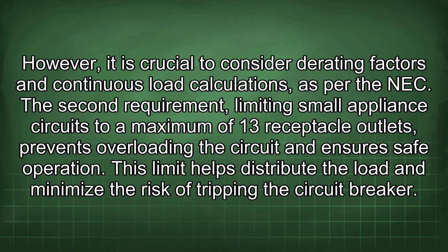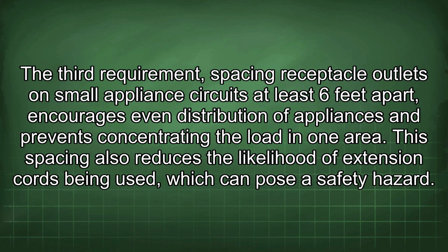The second requirement, limiting small appliance circuits to a maximum of 13 receptacle outlets, prevents overloading the circuit and ensures safe operation. This limit helps distribute the load and minimize the risk of tripping the circuit breaker. The third requirement, spacing receptacle outlets on small appliance circuits at least 6 feet apart, encourages even distribution of appliances and prevents concentrating the load in one area. This spacing also reduces the likelihood of extension cords being used, which can pose a safety hazard.